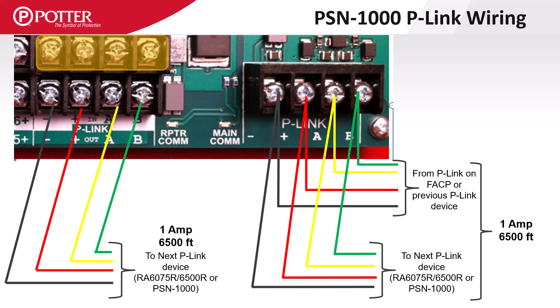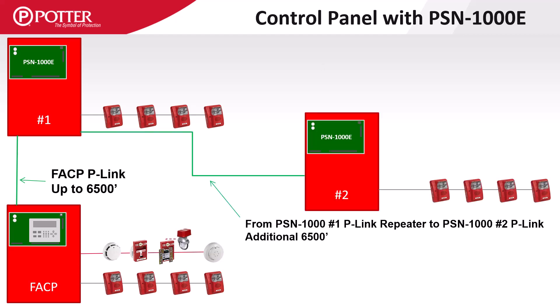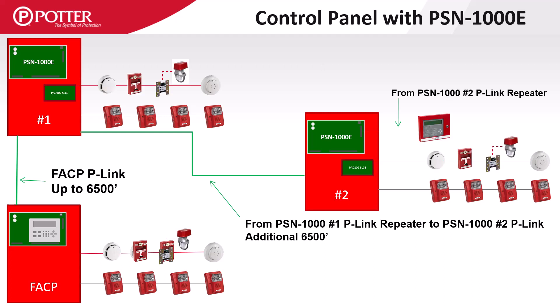There can be a lot of versatility when using the P-Link repeaters on the PSN1000. You can run the P-Link from the control panel 6,500 feet to the first power supply, and using the repeater terminals on power supply number 1, run up to 6,500 feet to power supply number 2. In addition to the notification appliance circuits, P-Link modules including SLC expansion cards can be remotely located in the PSN1000-E enclosure.